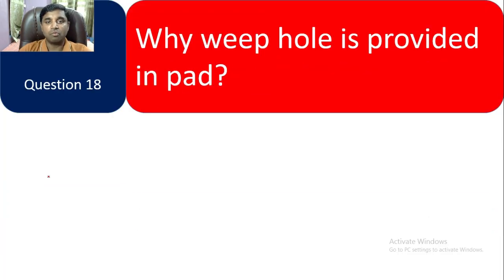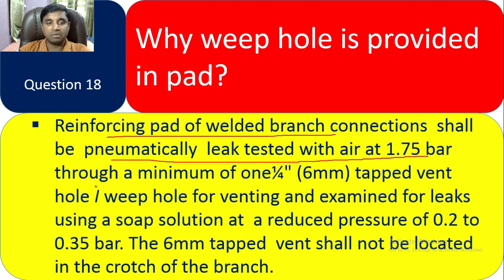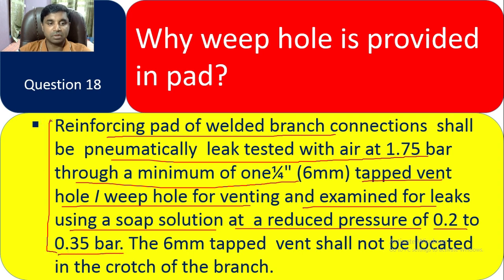Question 18: Why is a weep hole provided in a pad? The reinforcement pad of a welded branch connection shall be pneumatically leak tested with air at 1.75 bar through a minimum of one 1/4-inch tapped vent hole or weep hole, for venting and examination for leaks using a soap solution, at a reduced pressure of 0.2 to 0.35 bar. The vent hole shall not be located at the crotch of the branch.